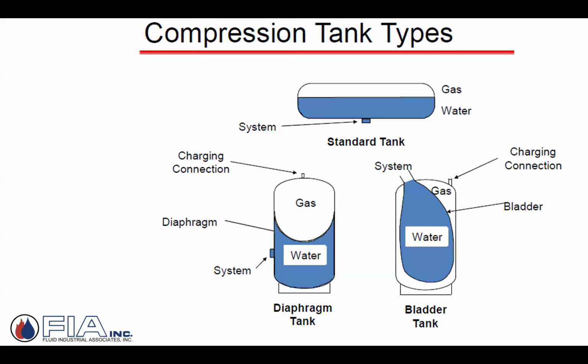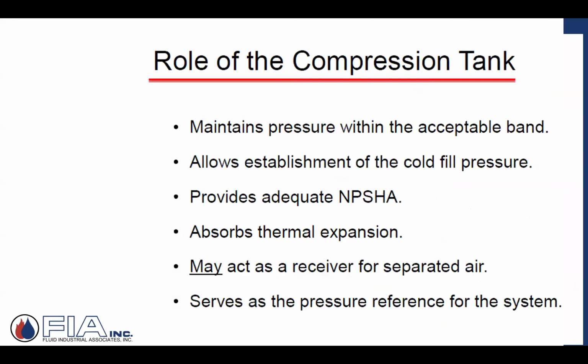But again, the industry's moved on and said, look, they're all expansion tanks. Fine. Why do we need them? What's the purpose? We're going to do a much deeper dive next week. We'll get into air management, or the third week, I guess it is. But the role of a tank is this: maintain pressure within an acceptable band. I've got to fill the system. I don't want my relief valves active. I want it closed. I don't want water dumping on the floor every time my boiler plant fires.